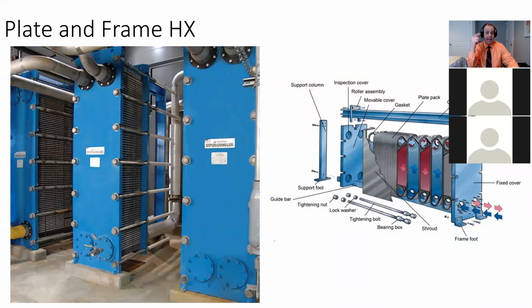They're made so that you can clean them. Theoretically, you can take them apart and then mechanically clean off any gunk that's in there or any things that might be clogged up, but they leak like crazy. They're very hard to make so they don't leak. And they do also suffer from the same thing that brazed plate heat exchangers do. They have high pressure drops. You get good H's, but the trade-off is pressure drop.